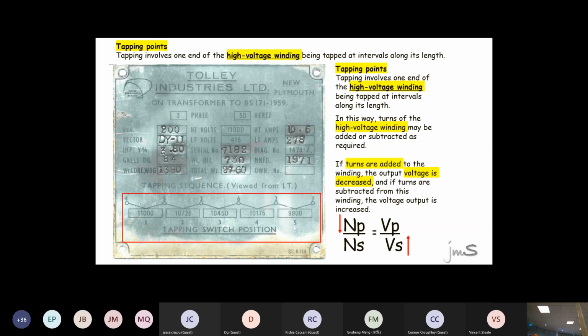But to add turns is very costly, because you'd have to add more turns on the transformer. So the moral of the story is we put the tappings on the primary side so we can keep dropping turns to increase the secondary voltage, because voltage and turns are proportional, but primary and secondary are inversely proportional. So if I drop the turns, I raise the voltage.